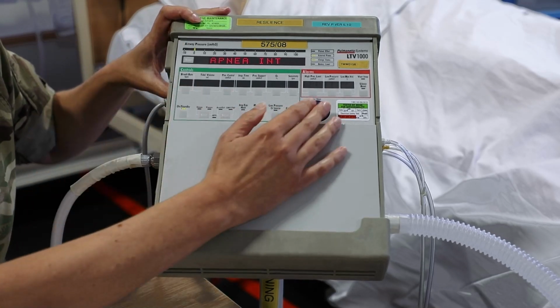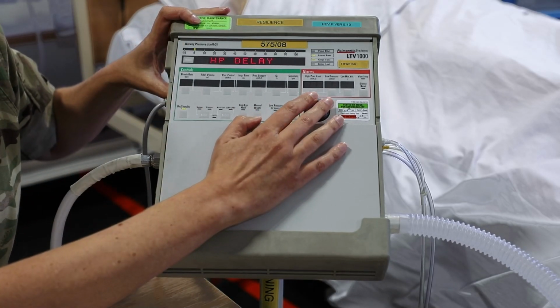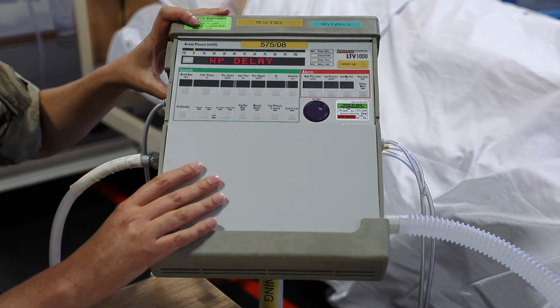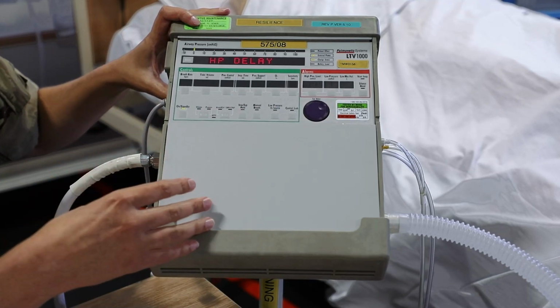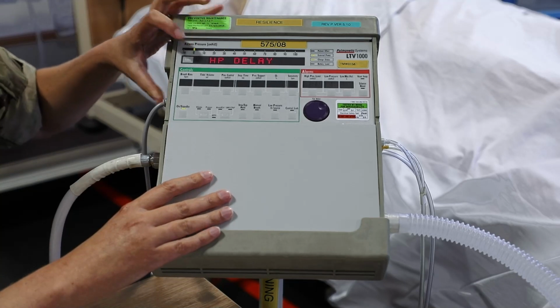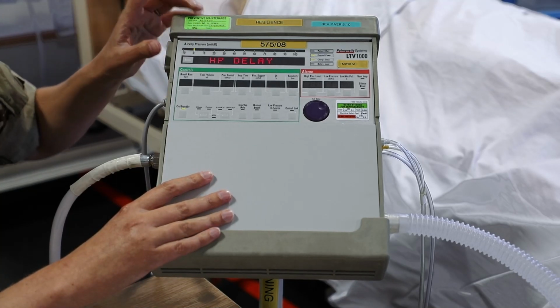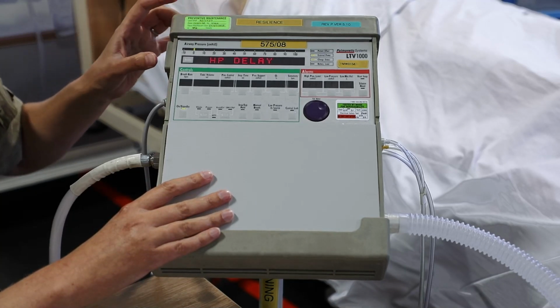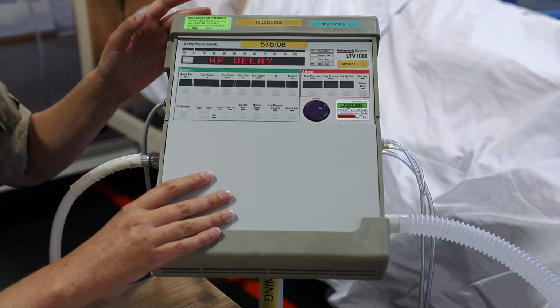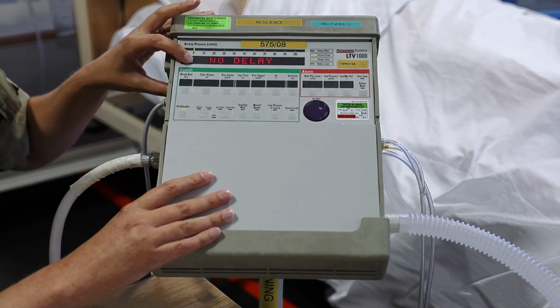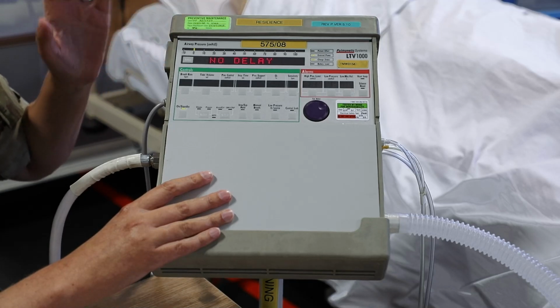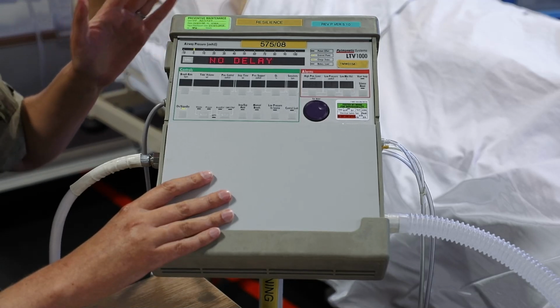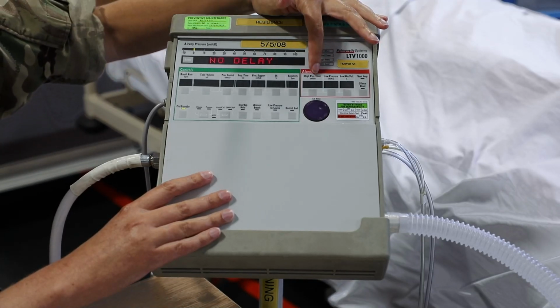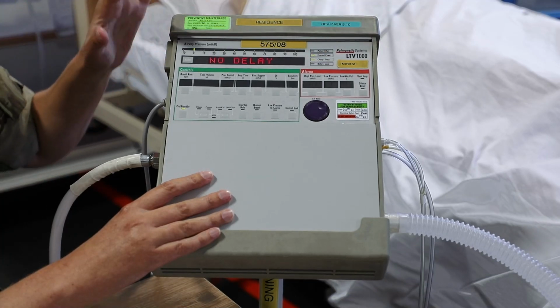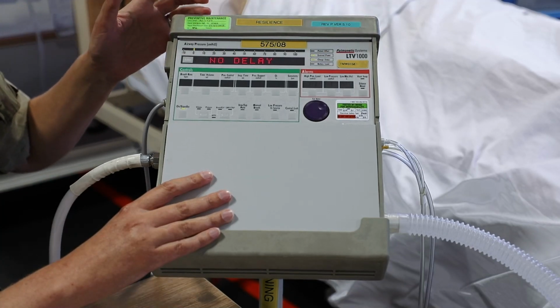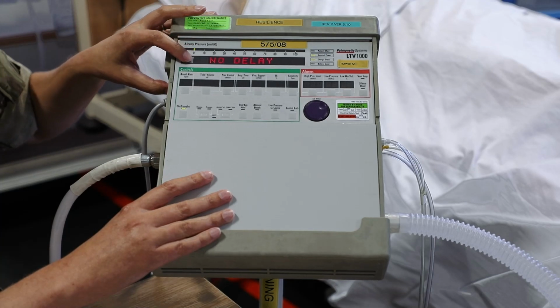Press select to go into the upper menu and then turn the dial to the right to go to the next option. Here we have a high pressure delay, and this is an alarm that would become audible if there was a high pressure in the vent circuit. And we effectively don't want any delay on that. If there's any high pressure, so pressure above the high pressure limit that you've set on the alarms, we don't want any delay before it alarms at you. So just have that set at no delay as standard.